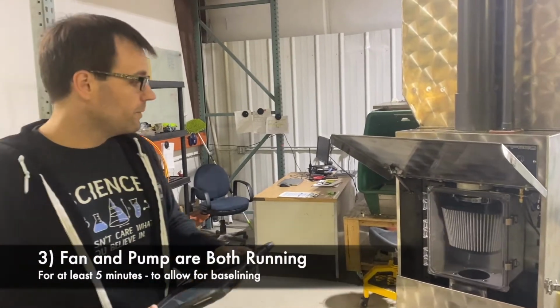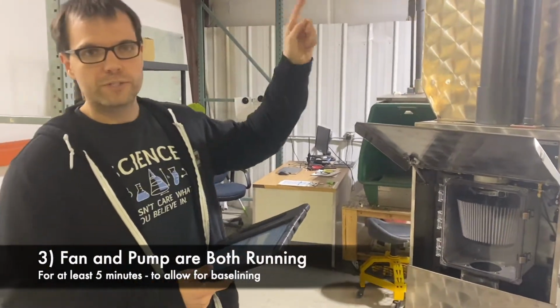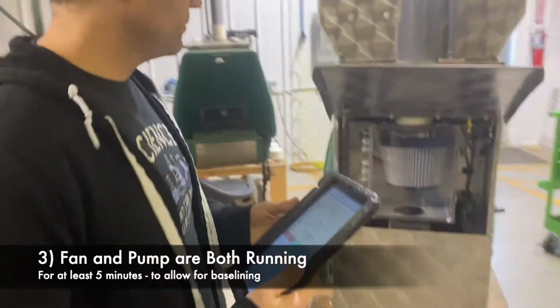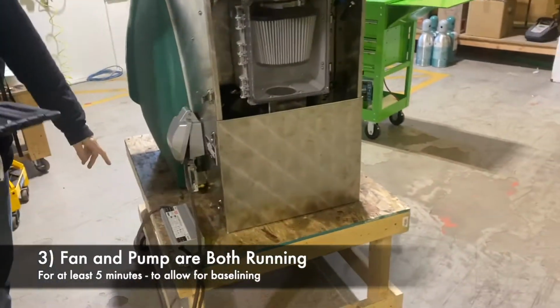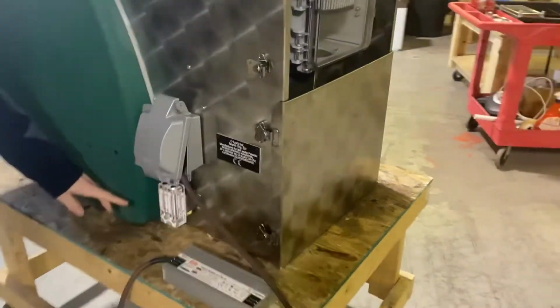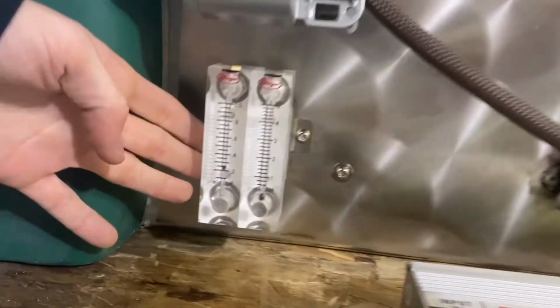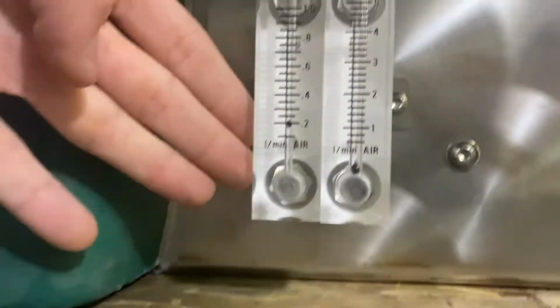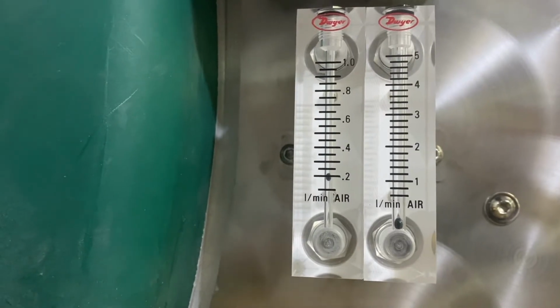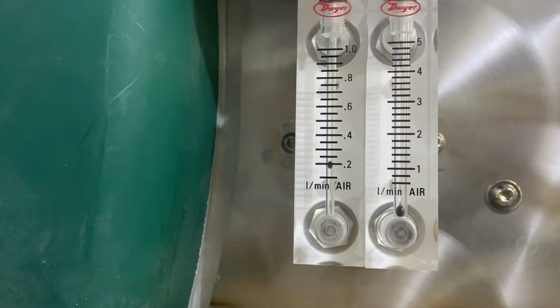All right, the next thing, we want to make sure that our fan is on, which right now it's not. And we also want to make sure our pump is going, which right now it's not. And we can tell because on the new systems, we have our flow gauge right here, and you can see that the gauge is at 0 right now.